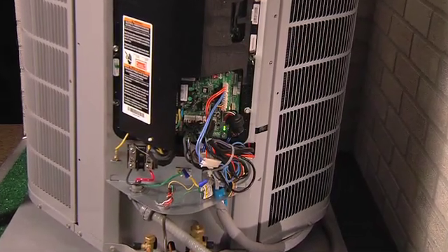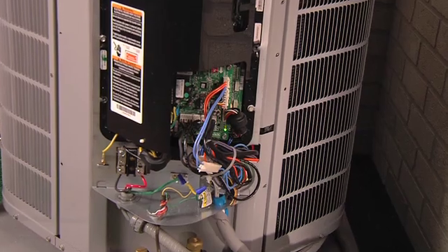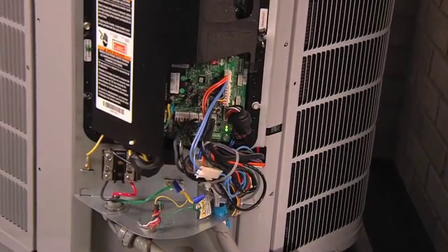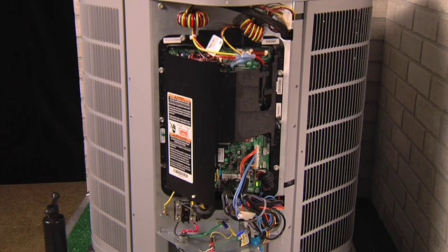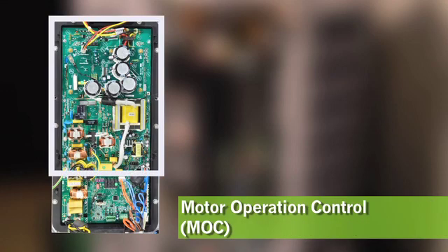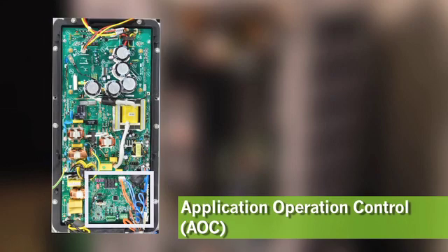This is the inverter, which coordinates operation of the variable speed compressor and fan motor. The inverter drives much of the high efficiency performance and comfort achieved by these units. There are multiple circuit boards in the inverter tray. The motor operation control, otherwise known as the MOC, and the application operation control, known as the AOC, are the two primary boards identified. The AOC is a field replaceable board mounted on the inverter tray. This is where the system status LEDs are located for troubleshooting.